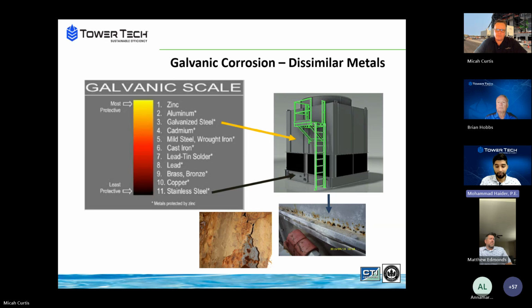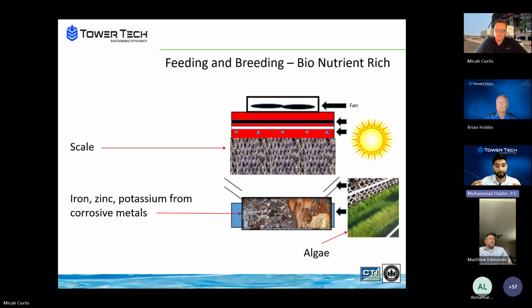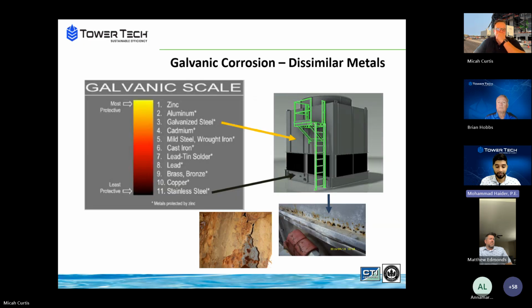you're going to have a lot more issues. So to round that topic out, regarding algae and biofilm, as we know, cooling towers are open to the air and atmosphere, and cooling towers are actively pulling in air from the atmosphere. As they actively pull in air, they're pulling in organic particles, dust, pollen, and exposure to sunlight is a direct cause of that. So you have these organic particles that are then exposed to sunlight, and that's a direct cause of algae growth. So that's the two aspects on that slide.